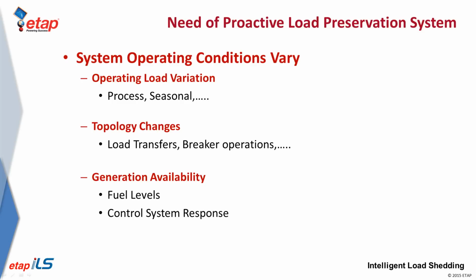At the time of performing load shedding, it is required to analyze how much generation we have available. This has a direct impact on the available generators to respond to sudden changes. A reliable and intelligent load shedding system can help you reduce such costs by reducing required spinning backup generation. Changes in your governor settings also impact the way the system responds. They must be taken into account when transient conditions occur.